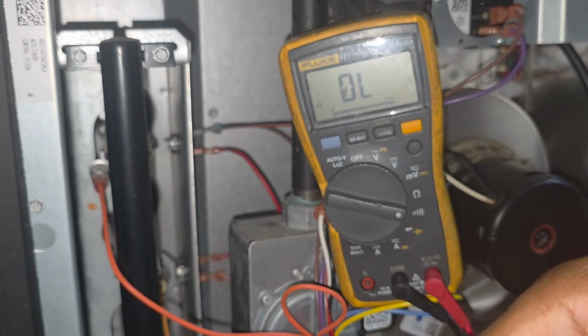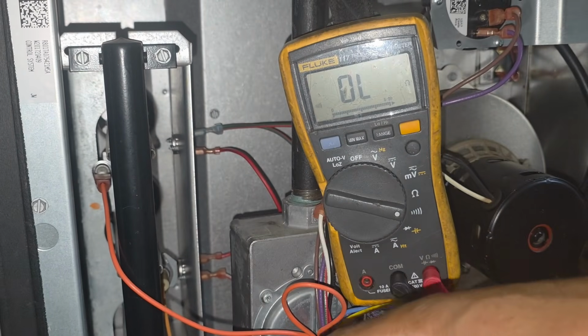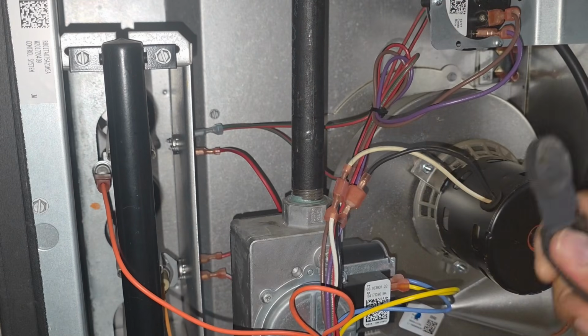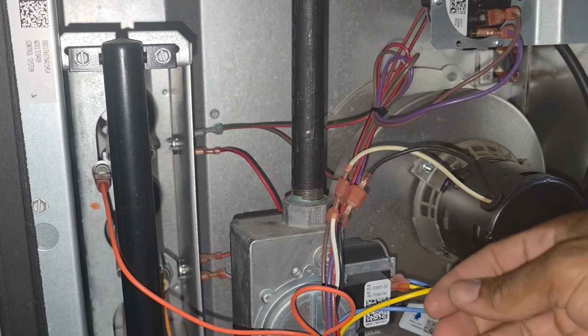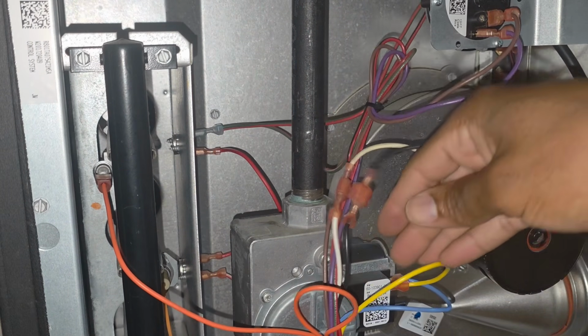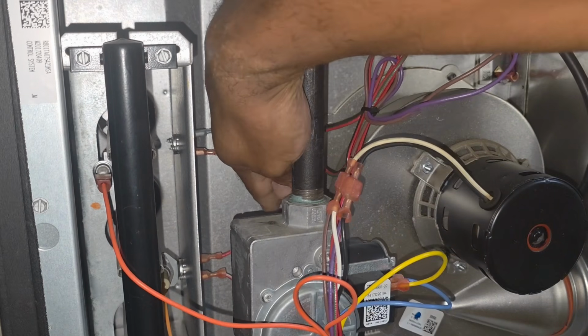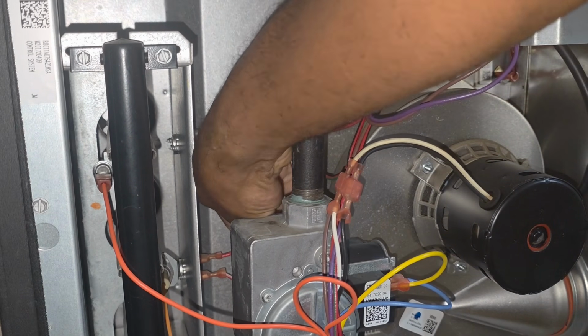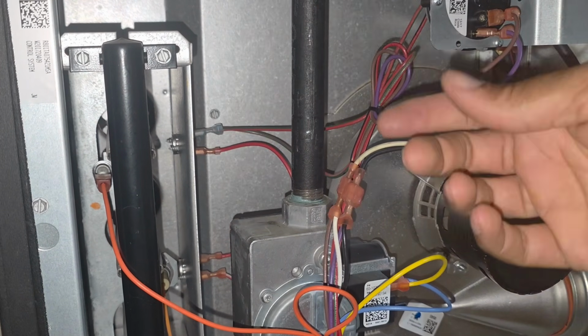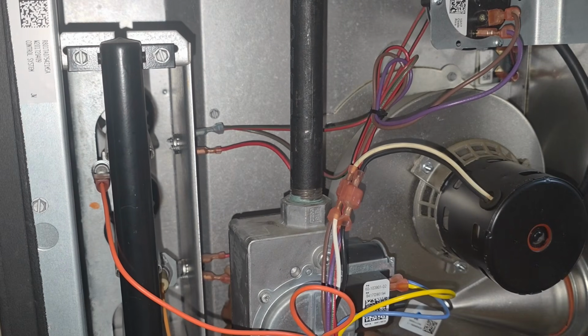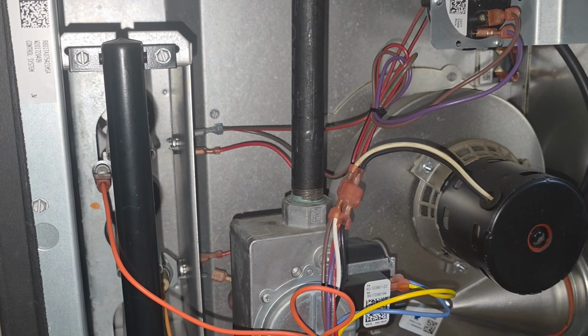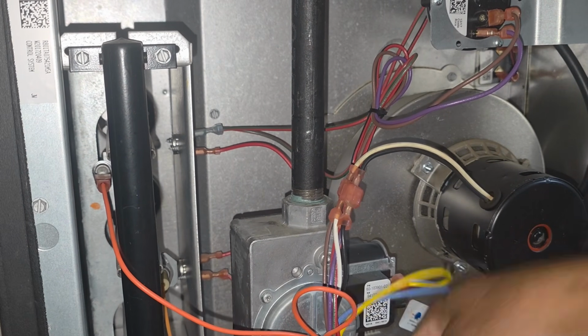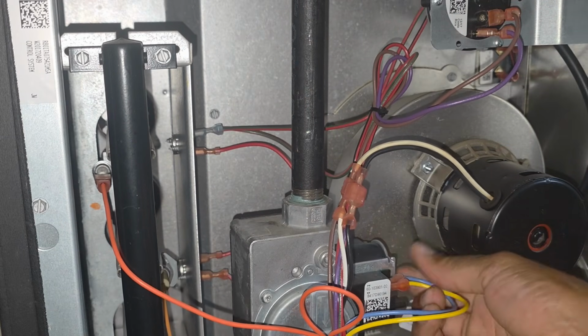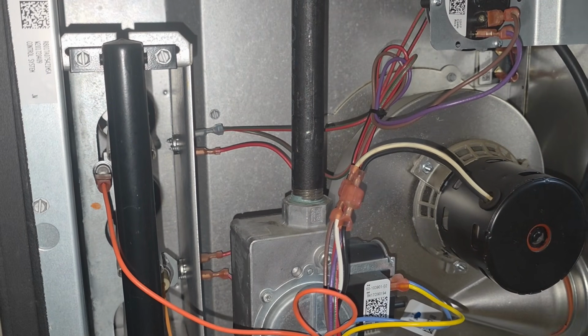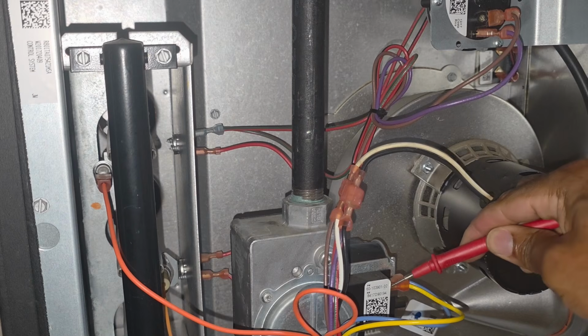So I'll put that one back on. I'll call for heat again, let it do it again. I'm like, man, it started cutting off. So then I would go down. Because sometimes it takes 10 minutes before you go through a cycle. So I would take these back off, take the bottom two off, and I would check it for continuity. So I take this. Oh, it's hot. I don't want to burn myself and leave it on, but same thing. Okay, this is the gas valve, but if you were checking the gas valve, you would do the same thing.